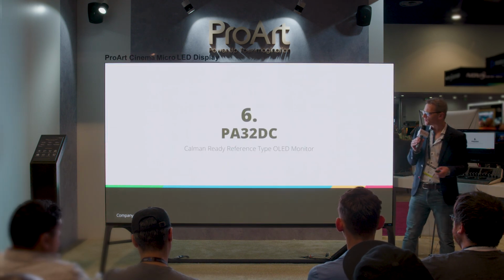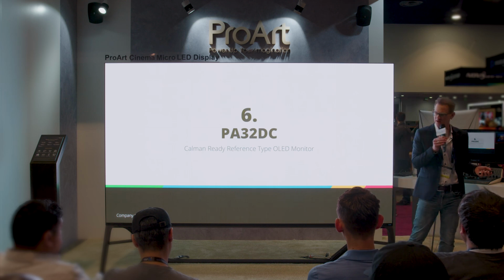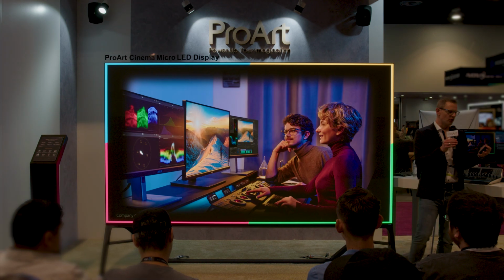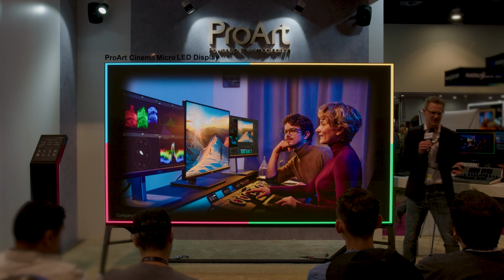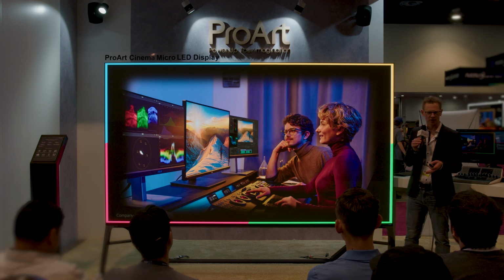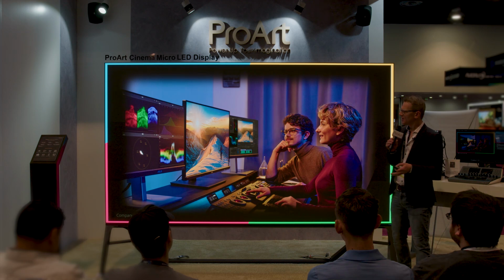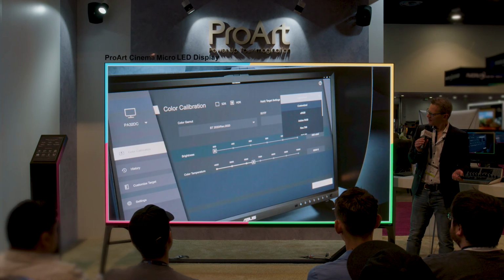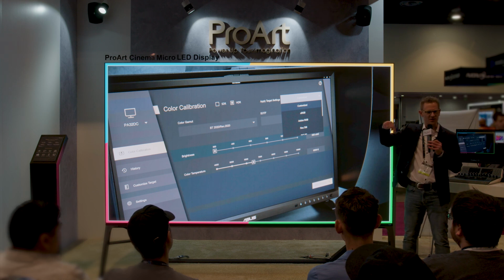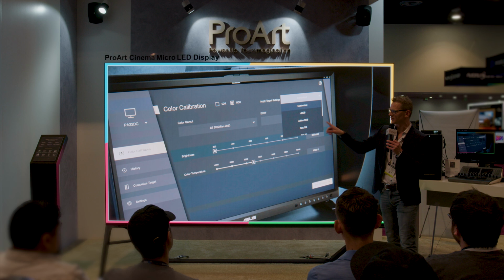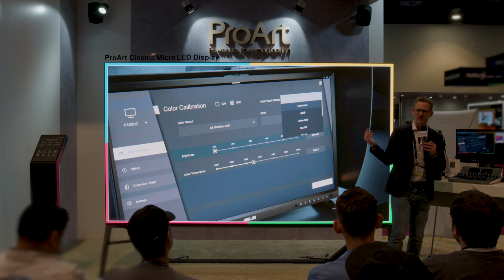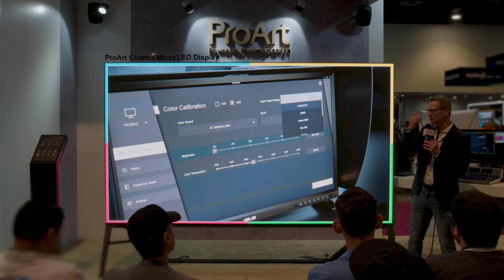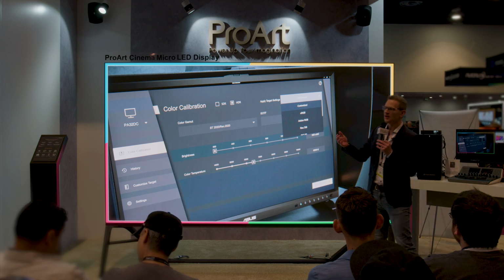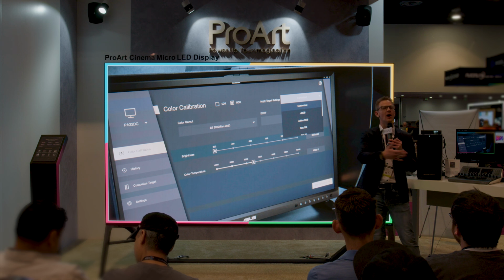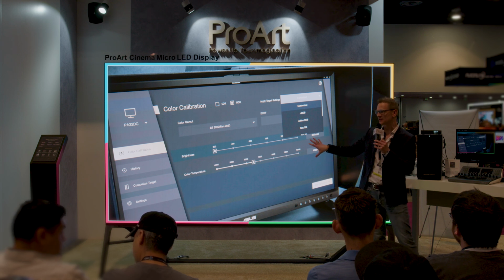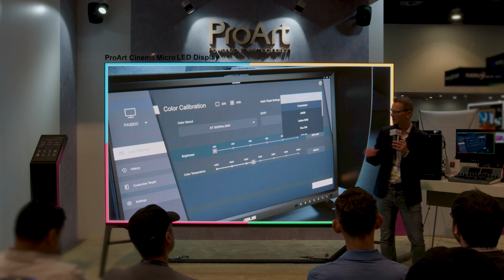So the PA32DC then is kind of a reference type OLED display. So it's made for colorists, or it's made for DITs on set, and VFX people who actually want to have a high-end monitor they can somehow trust. That's a very important thing. So it has even its own software. It has a built-in meter as well. So if you would not want to use one of our meters, you could even use the built-in meter. And it also has its own calibration software, by the way. So why would you still want to use Calman? Well, I told you, because most studios have Calman already, and they do all the other monitors as well with Calman. And so it's neat that this device, that display, also talks to Calman. That's one of the reasons.